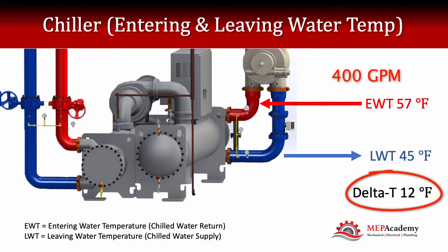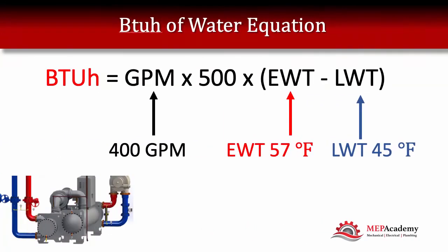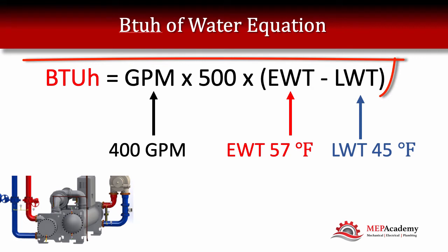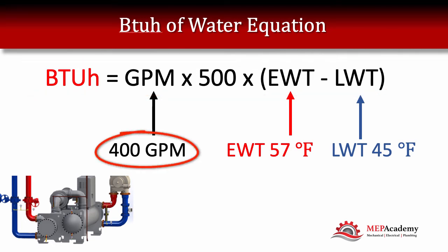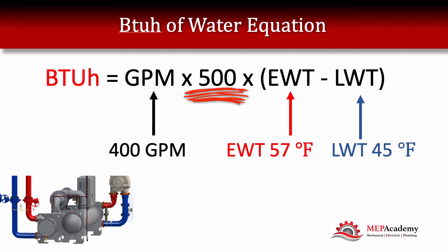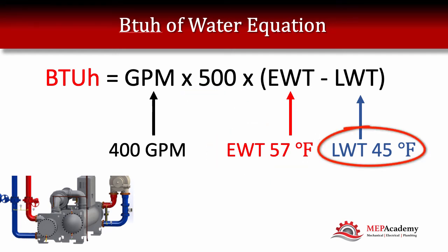With those values we can determine the tonnage of this chiller. The equation is BTUs per hour equal GPM times 500 times the Delta T. We measured 400 GPM, times 500, times the Delta T: entering water temperature was 57 degrees — chilled water return — minus 45 degrees chilled water supply, which gives us a Delta T of 12.